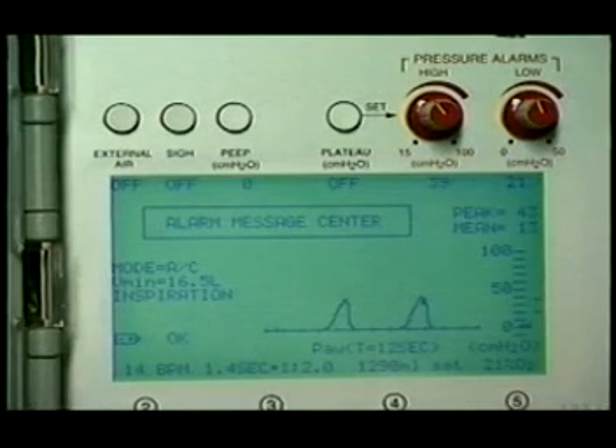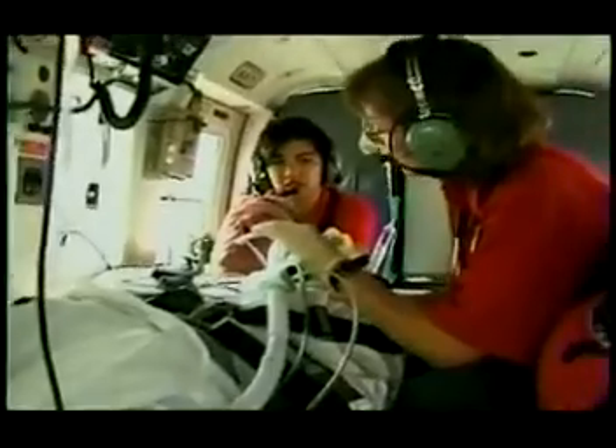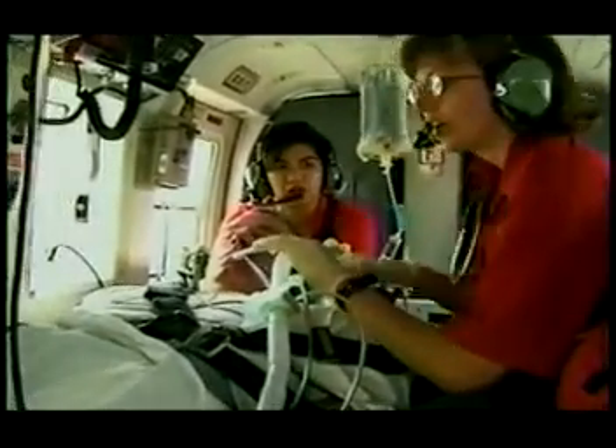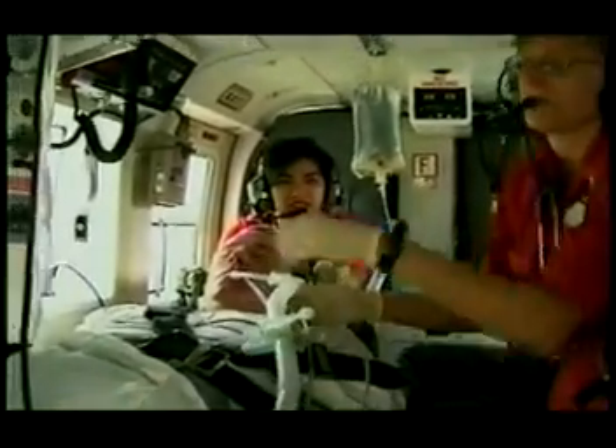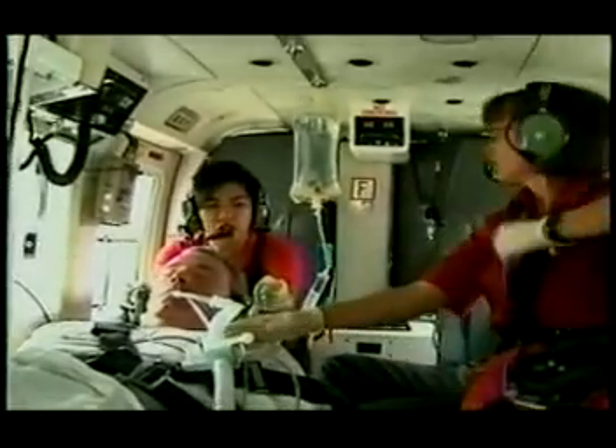The peak inspiratory pressure relief mechanism activates at the high pressure alarm control set point, which momentarily opens the ventilator circuit exhalation valve and dumps excess pressure to atmosphere. So, your patient is protected during each breath while the high pressure alarm is disabled until 4 consecutive breaths have been violated.